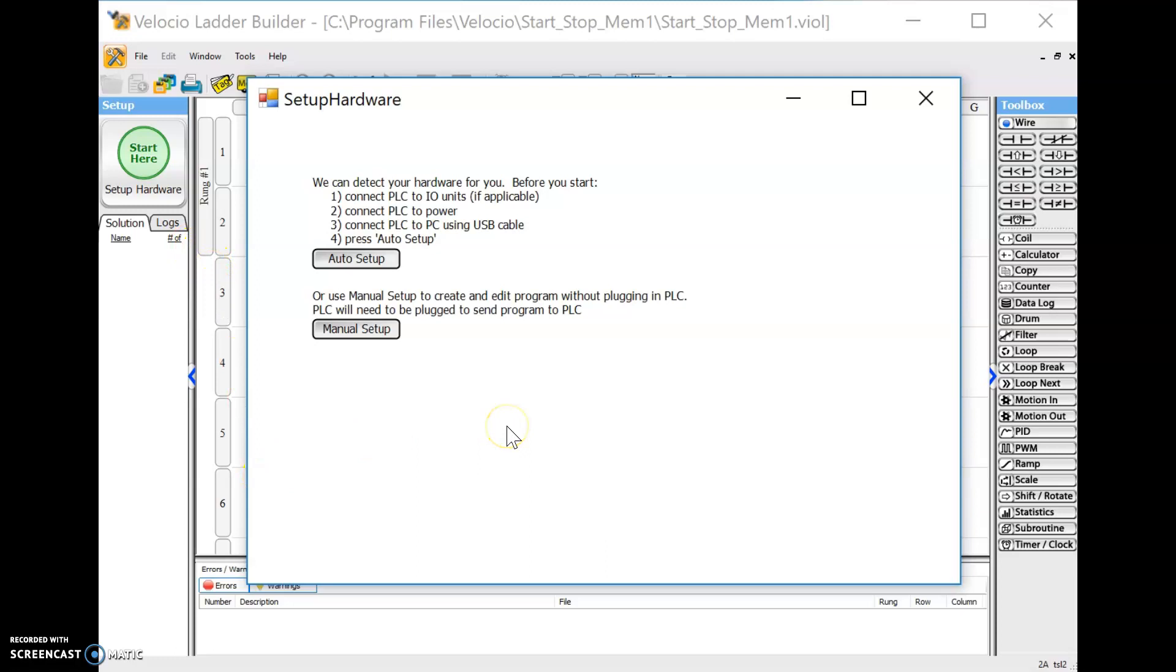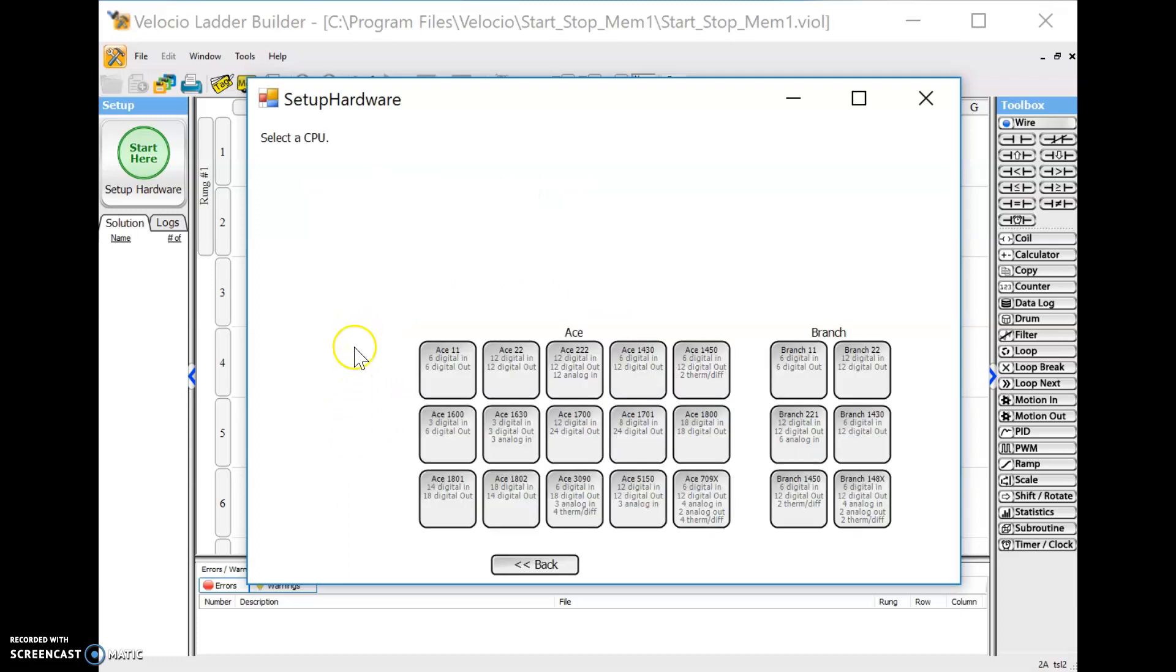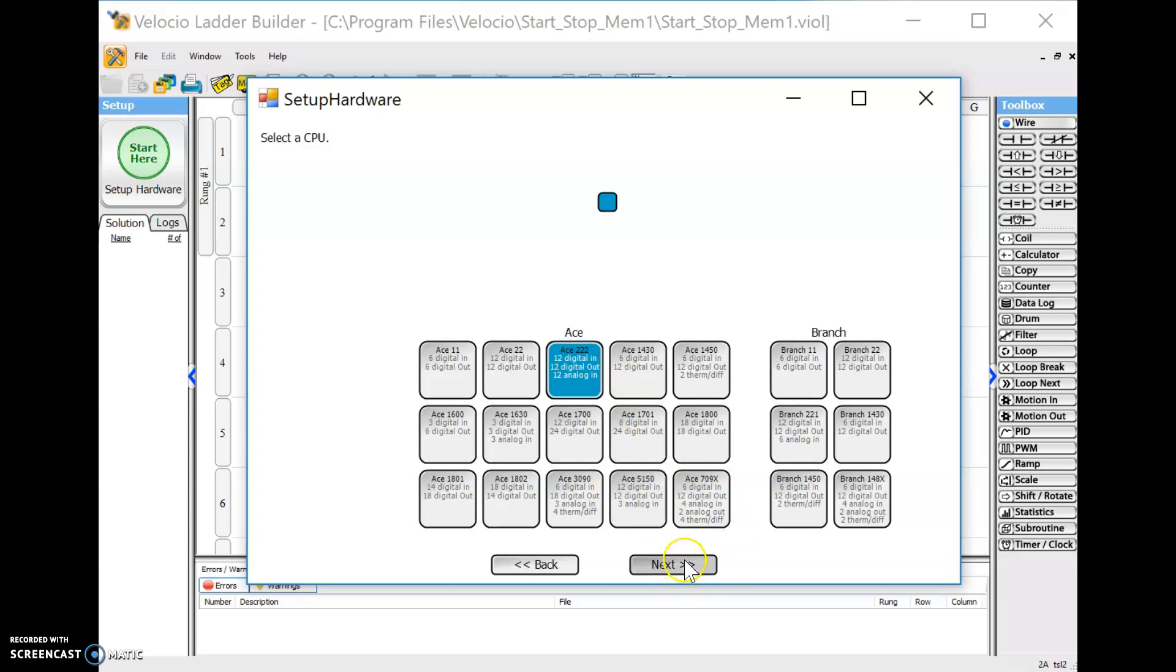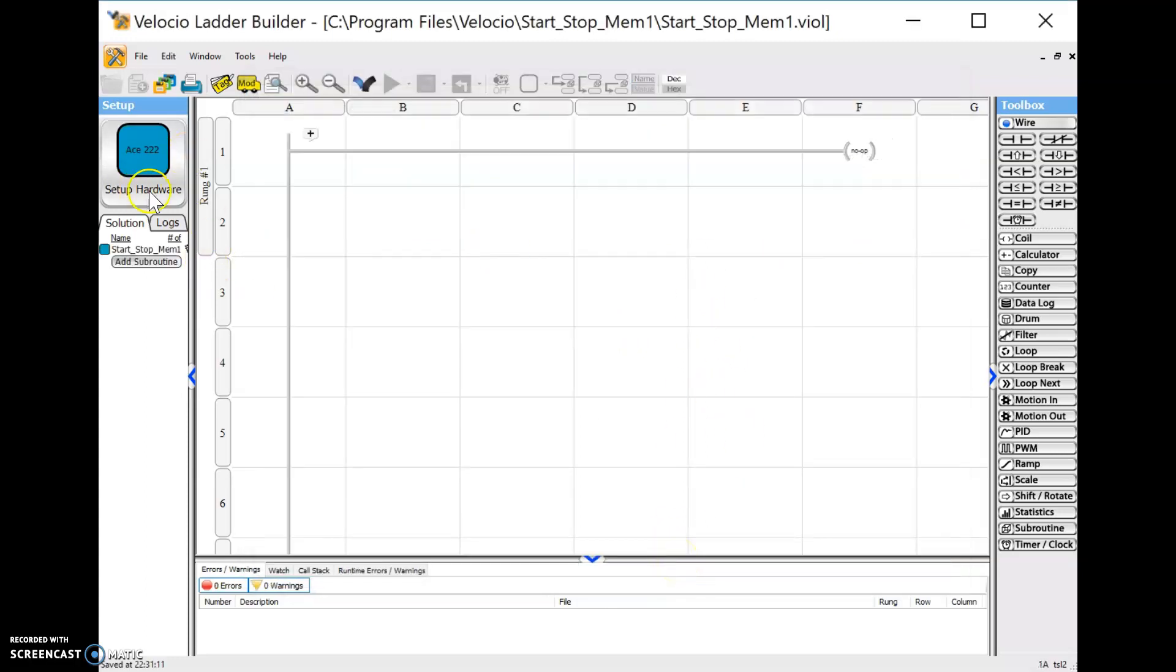When you set your hardware up, basically you're telling this program what type of PLC you have. Every PLC on this list is different. Now if we had the PLC with us and had the programming cable plugged in, we could click on auto and it would detect what it is. I don't have it plugged in right now. We'll save that for another video. We're going to go with manual today. I know for a fact the type we own is an ACE 222. Today we're going to be programming this bad boy. This one, we're not using any high speed counters or stepper motor outputs. So we're just going to skip those, leave them at none.